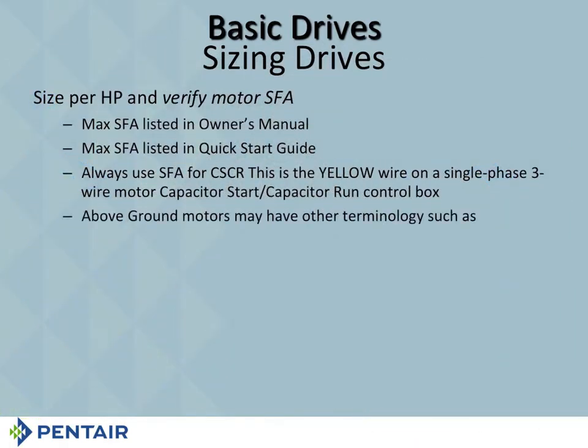Above ground motors have other terminologies such as max load amps, and these are for your smaller motors. I'm going to call them A.O. Smith, but the name has been changed to Regal, so you will be seeing that in the field shortly. Regal purchased A.O. Smith a good 1.5 years ago, and they're just getting around to changing the name. And they do use that term, max load amps. Baldor motors, which are 3 and 5 horsepower above ground motors, use the term full load amps. And of course, full load amps relate to the nameplate horsepower. It doesn't take service factor into consideration.